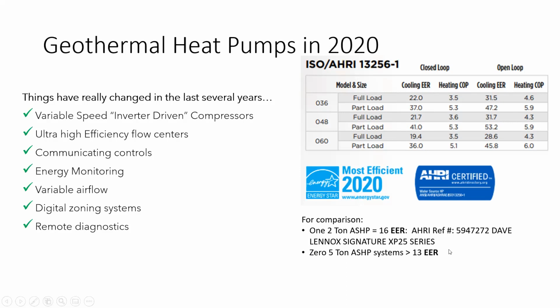Now that's performance at 95 degrees Fahrenheit outdoors. That's 13 EER. There are no 5-ton systems that achieve 13 EER at 95 degrees Fahrenheit. However, at 95 degrees Fahrenheit, you can see geothermal heat pumps are as low as 22, 19, and as high as 53. So that's a dramatic comparison right there.